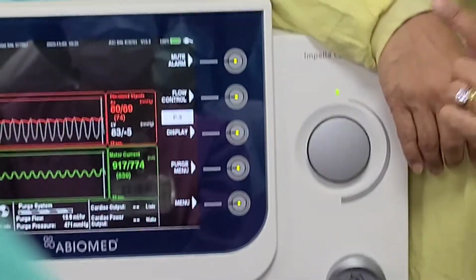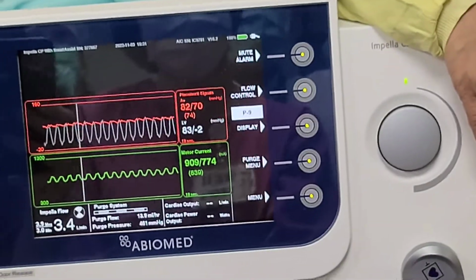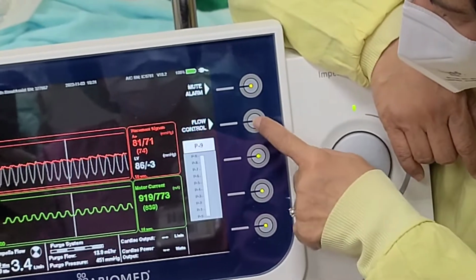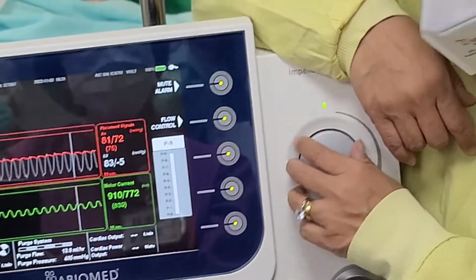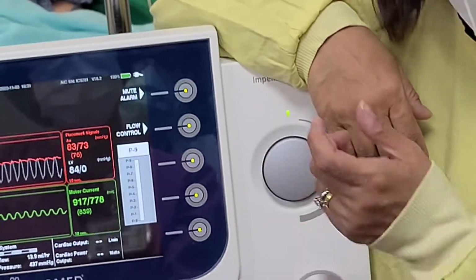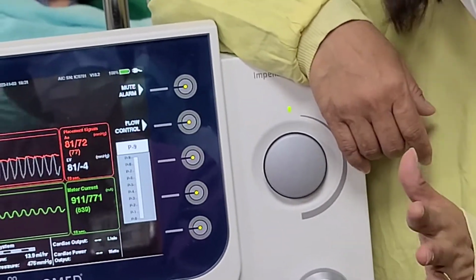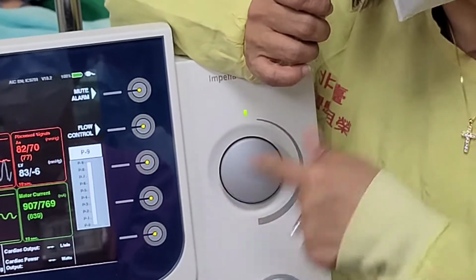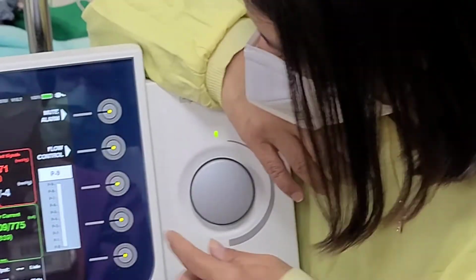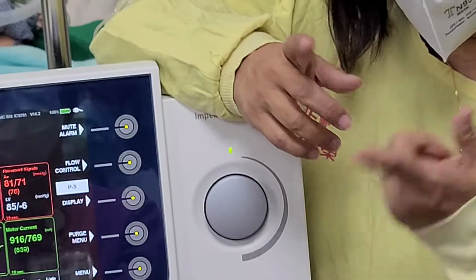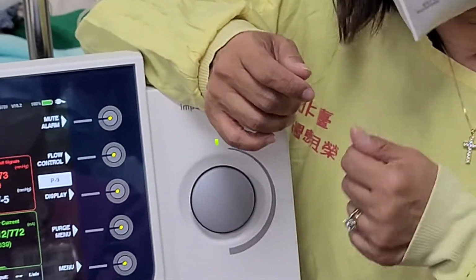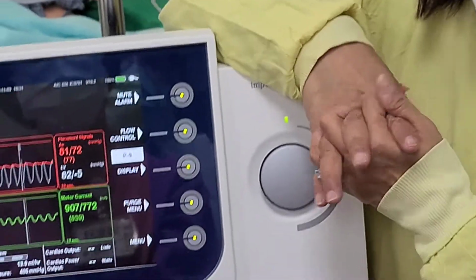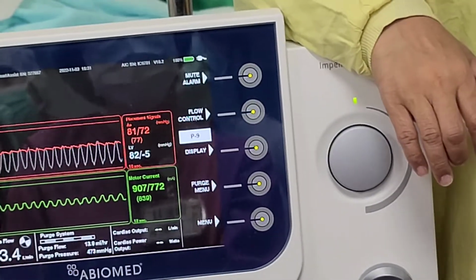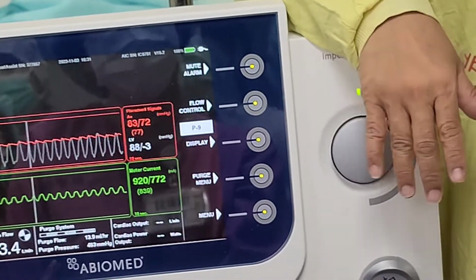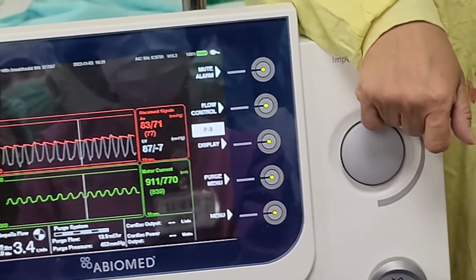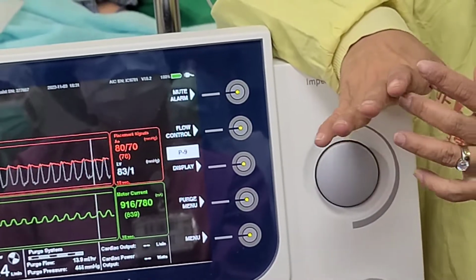With Impella, what you will do is drop the flow by 1 to 2 P levels. How do you do that? You go to flow control and turn this to P7 or P8. Nothing will happen if you don't press. You notice I'm not pressing because I'm not changing anything. So you turn the flow down a little bit to break the suction. Then you check the volume status. We normally say keep about 8 to 12, but because she's got ECMO, I think closer to 14.